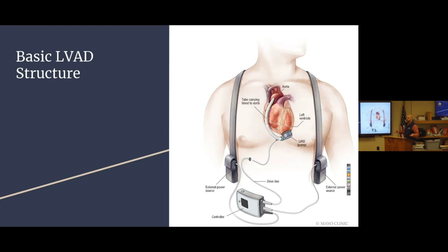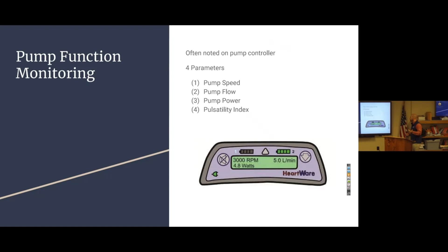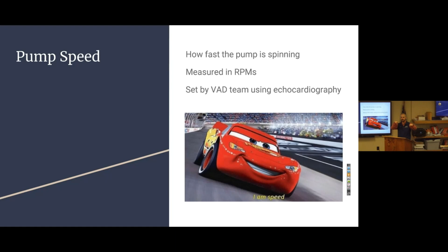There are pretty much 4 parameters that you're going to look at on these devices. This one's displaying 3. That 4th one, pulsatility index, sometimes is seen, sometimes not, depending on the device you're wearing. So that's pump speed, pump flow, pump power, and pulsatility index. So speed, this is how fast that device is spinning, okay? This is usually a set rate, and when you look at the device, this number is not going to be changing. On some devices, they got a little smarter, and to be a little bit more precise, this may fluctuate, but it should only fluctuate by like 100, okay? This is going to be in RPMs, or rotations per minute, and this is set in the hospital. They dial it in and out using echo to figure out how exactly they can get this patient their best amount of flow, okay?